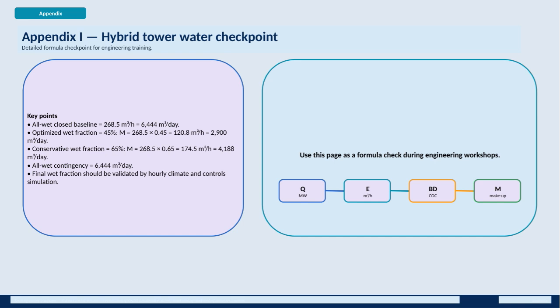The optimized wet fraction is set at 45%, resulting in a makeup water volume of approximately 120.8 cubic meters per hour, or 2,900 cubic meters daily. A more conservative estimate uses a 65% wet fraction, leading to a higher makeup flow of 174.5 cubic meters per hour, translating to 4,188 cubic meters per day. In any case, the contingency plan still accounts for the full all-wet flow rate of 6,444 cubic meters per day.